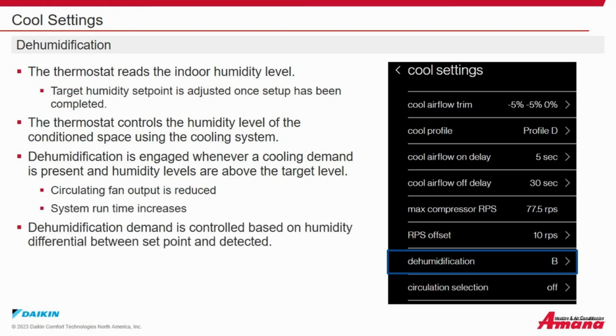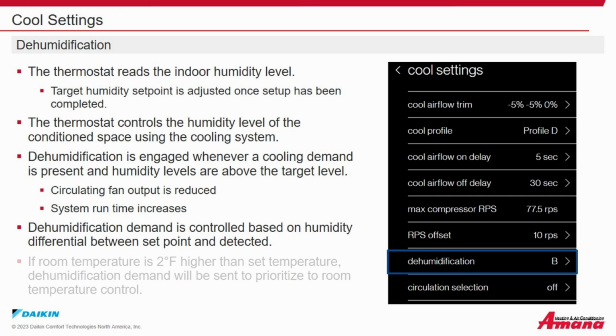Dehumidification demand is controlled based on humidity differential between set point and detected humidity level. If the room temperature is 2 degrees Fahrenheit higher than the set temperature, dehumidification demand will set the priority to room temperature control.